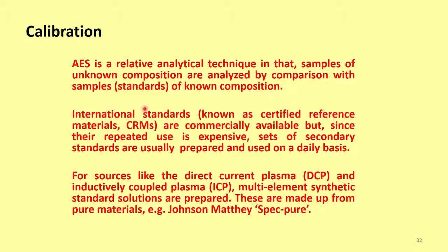A calibration curve is made of the concentration versus response curve. Okay. So, in atomic emission, samples of unknown composition are analyzed by comparison with samples of known concentration. That is the basis of all spectrophotometric procedures.